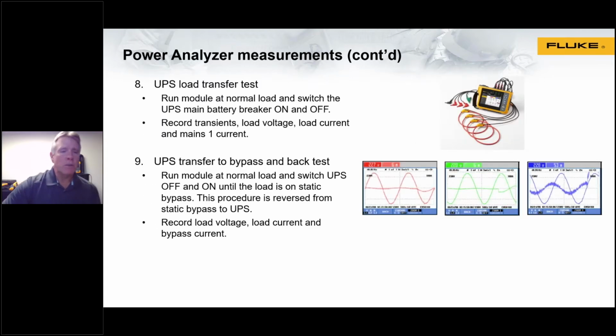Our last 2 tests, number 8 and 9, are a load transfer test and then a transfer over to bypass and back test. Again, initially upon commissioning, you're doing all this as a pre-installation, prior to connecting your critical loads, and using load banks to perform the tests. And here we have some examples. You would run the module at normal load, switch the UPS main battery breaker on and off, and then again record transients on all 3 phases, and look at load voltage, load current, and mains 1 current for proper operation.